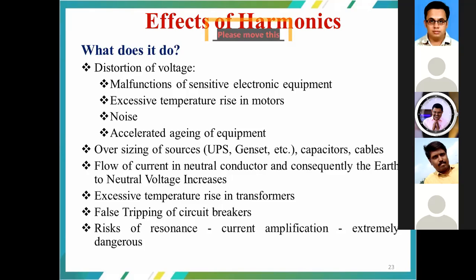And it may require the oversizing of the sources, which includes the UPS, generators, capacitors, cables, and the associated components. And again, the harmonics may result in the flow of current in the neutral conductor, and consequently the earth to neutral voltage increases. As far as the IEEE standards are concerned, the earth to neutral voltage is between 5 to 10 volts. If it exceeds 10 volts, it leads to overheating, and it may result in fire hazards.